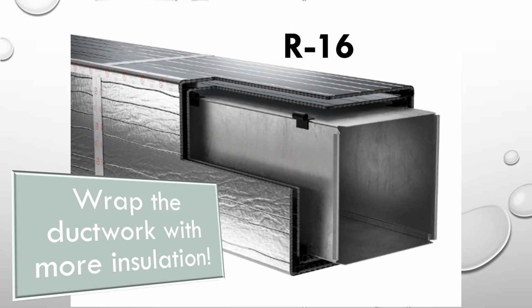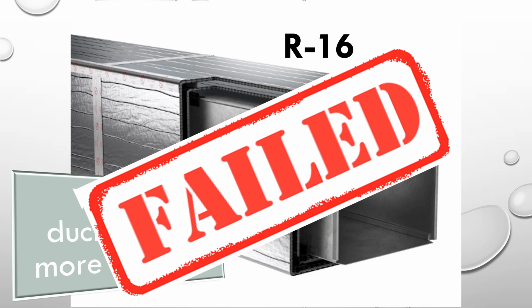All right, so the last idea we had to fix the ductwork condensation issue was to wrap the ductwork with more insulation. A typical duct system trunk line in an unconditioned area is R8. So we thought, let's rip the vapor barrier off of another sheet of R8 and wrap the ductwork again to form R16. We're thinking, doubling the code, we should be able to double our chances and not have any issues, double wrapping this trunk line and forming a really big insulation blanket around the cold duct system. This did help, but it did not stop our condensation from happening, which is what we're trying to achieve. We're trying to stop condensation from forming on the outside of the ductwork. So this also was a fail.